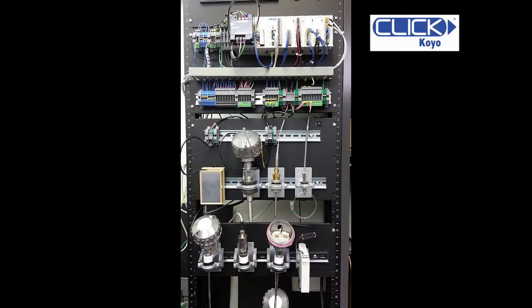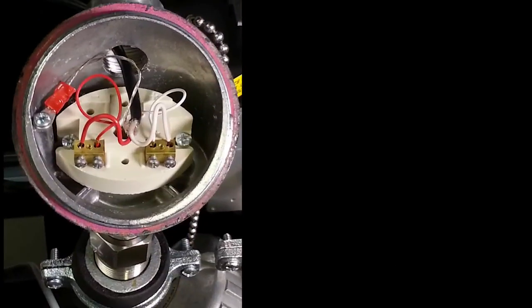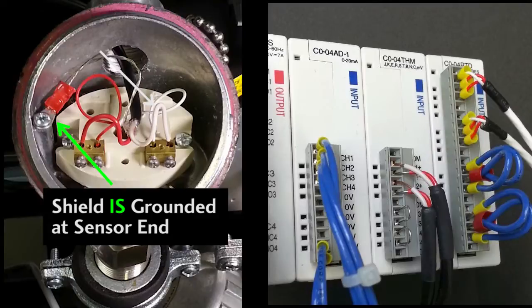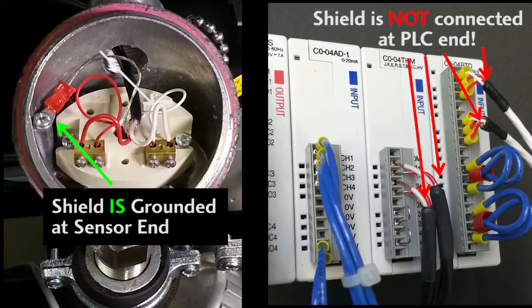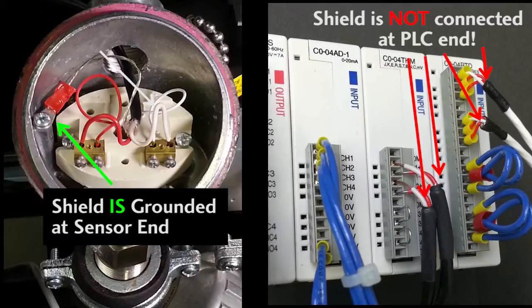They are wired exactly like the block diagram shows. The cable shield is grounded only at the sensor end, not at the PLC end. In general, you'll always want to ground the shield at the signal source end and definitely at one end only. Otherwise you'll end up with another current path which could create a ground loop and actually make things worse than having no shield at all.